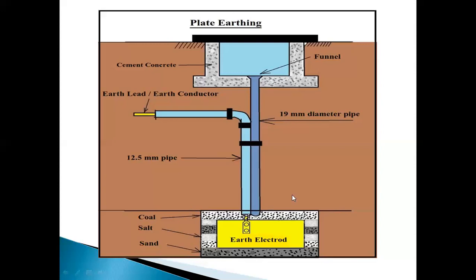The space around the earth plate is filled with coke or charcoal and salt in alternate layers, as we have used in the pipe earthing process. Why? Because this combination of salt and coke will reduce the resistance of the earth. This is done for a distance of about 15 centimeters around the plate to increase the dampness and moisture around the plate. Not only does it decrease the resistance, but due to the presence of salt, it also increases the moisture of the earth's surface.